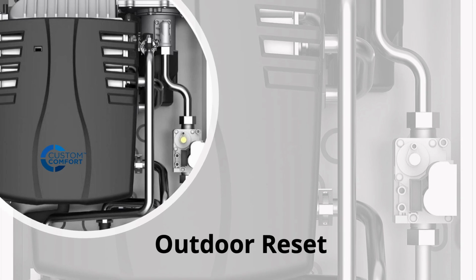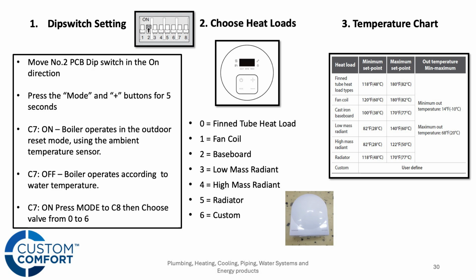Setting up the boiler, startup there. Outdoor reset, like I mentioned before: the outdoor reset sensor is going to come with the heat only boiler. It's available as an accessory for the combi boiler. If you're setting that up and you're using it on either one of these boilers, you are going to go into the installer mode to do that. So that's the Mode and + buttons for 5 seconds. After that, you're essentially going to choose what type of radiation or heat emission you have in the house, whether it be baseboard or radiators. We're going to tell the boiler what's going on to set that outdoor reset curve.